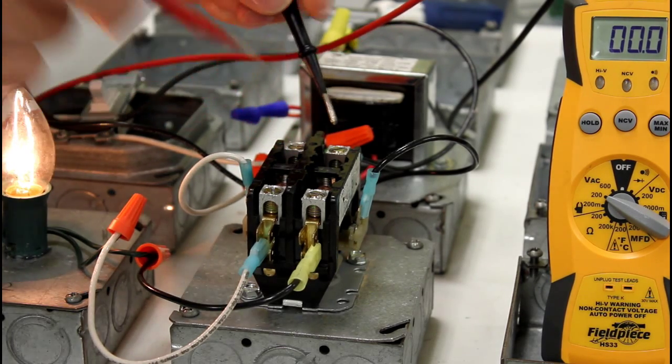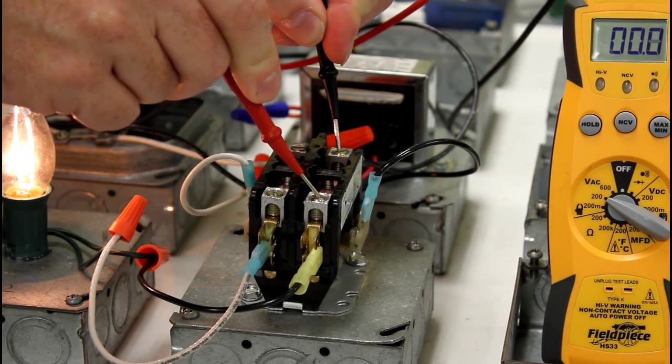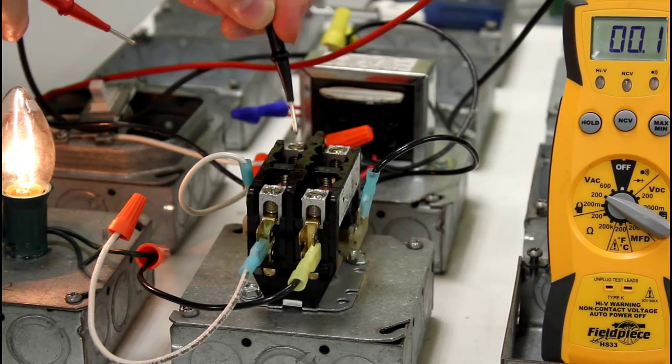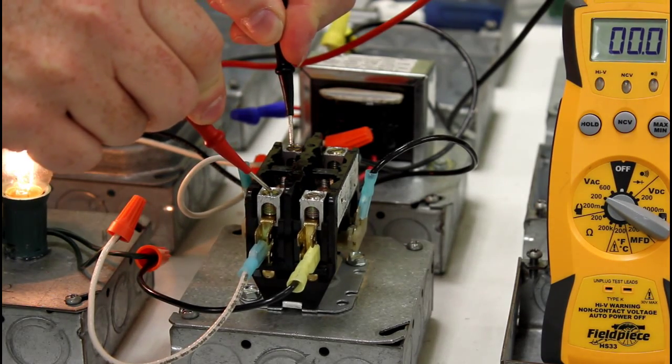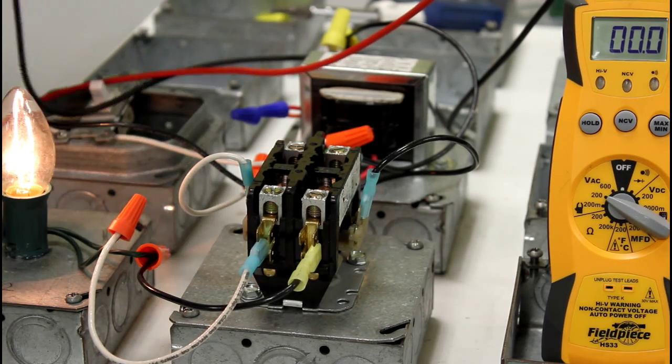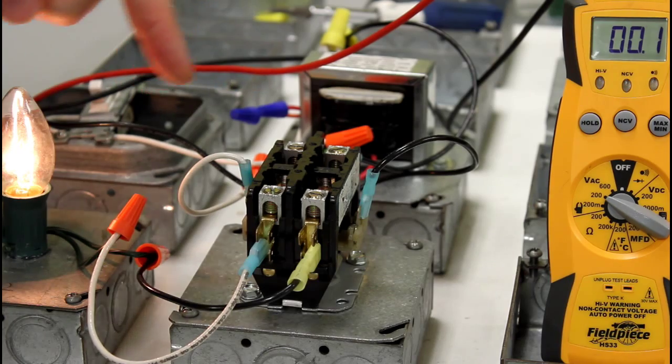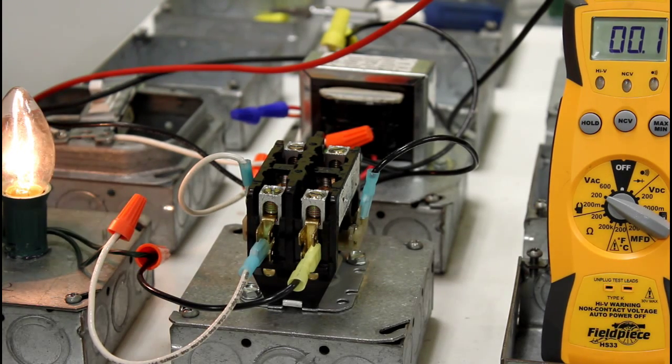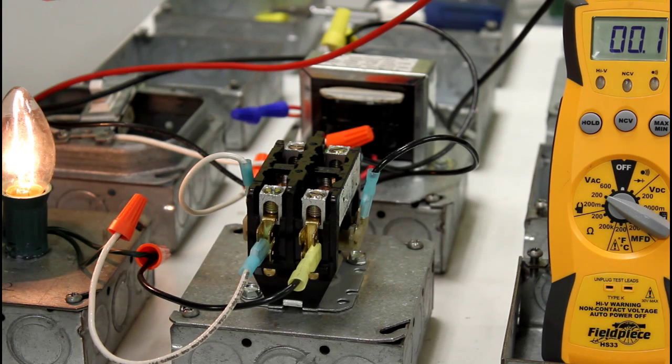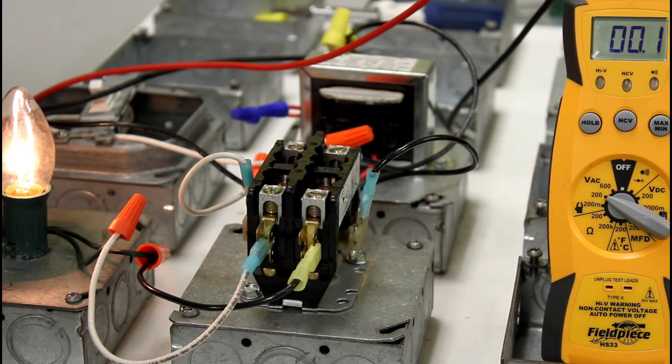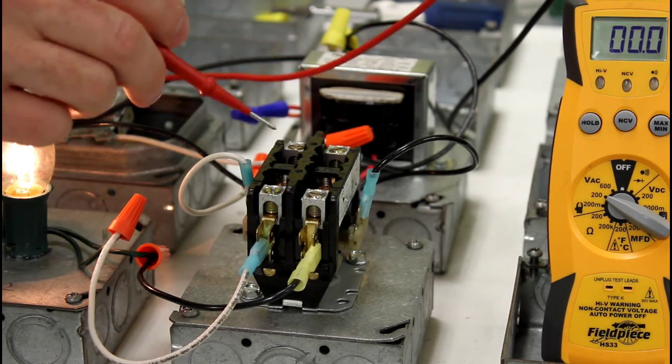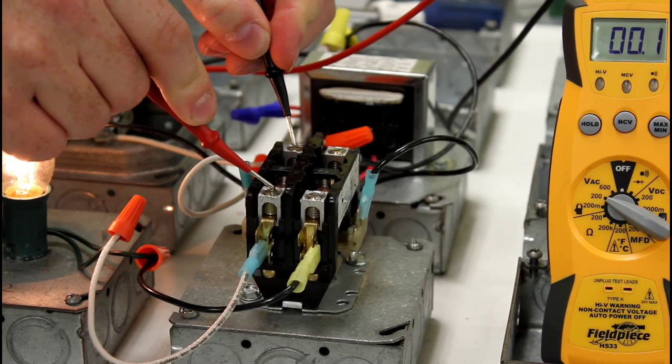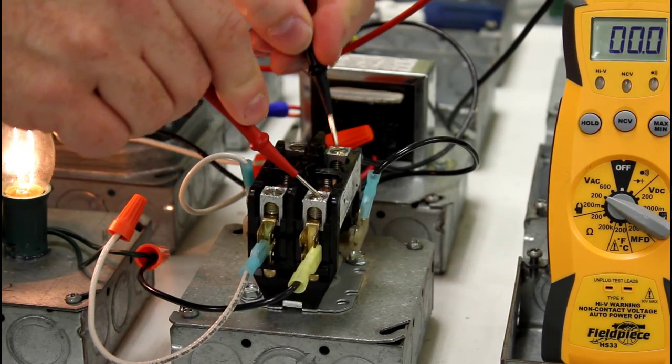Another check that we can do is check right across each contact. Here's contact number one. If I check from one side to the other, I should get zero volts, and I do. If I check on the other side on contact two from line to load, I also get zero volts. That's what I should have. Anytime you start getting a voltage drop across that contact, it means that it's pitted and needs to be replaced. Anytime you have more than about half a volt on high efficiency systems, you're going to need to change that out. On a normal system, if you get over about a volt, volt and a half, it's time to change these out. Right now you can see this one's in good shape. Got zero there, got zero there.